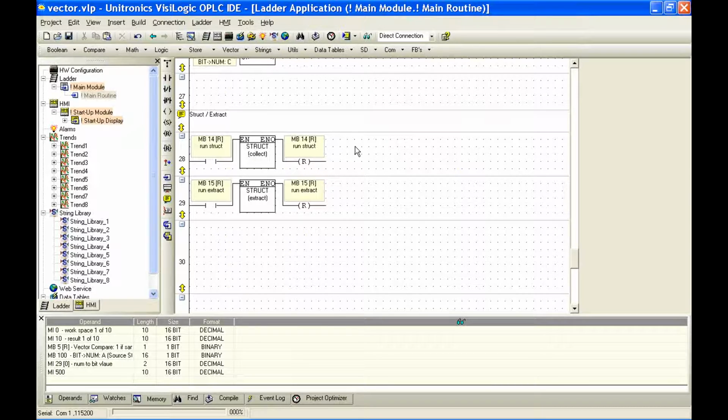Now again, as we pointed out, this isn't really a limitation. If you consider Modbus, if we want to get mixed data, a memory bit, a memory float, and a memory integer, there's 3 separate commands. But if we package or struct our information into one register type of a vector, we can send multiple pieces of information in a single command. So this cuts down on time it takes to transfer information, and it cuts down on transmission overhead in general.